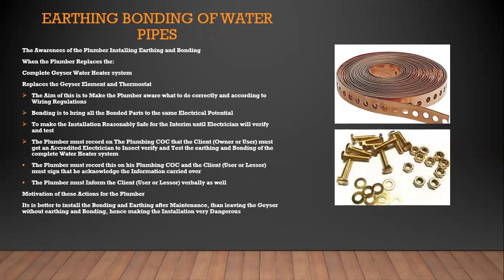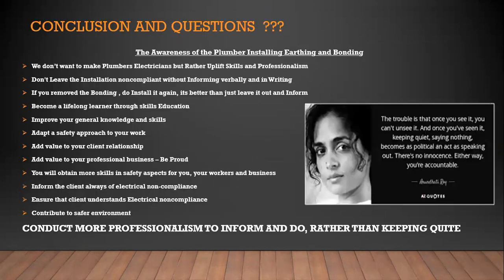Here we look at what type of bolts and nuts to use for the bonding straps. You have to use copper, not galvanized steel or gutter bolts like we know it, because there's a chemical reaction between the galvanizing and the copper. So we need to use the correct materials, and I address this quite a lot in the training material as well. So there's conclusions and questions.